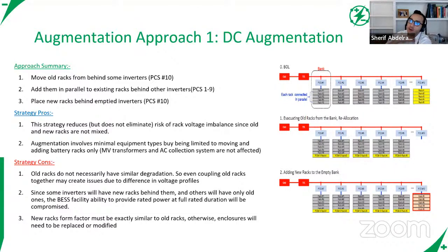It's as if you're adding an entire additional layer of inverters, really, because on a dollars per kW standpoint, they are at a similar price point. So again, it goes against the whole reason we're doing augmentation. So personally, not a big fan of this solution, but there could be cases out there, and there probably are cases, that make sense. Just depends on the use case.